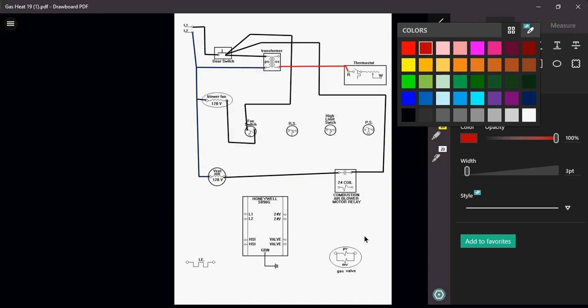Okay, our high limit switch, that's going to be a safety that's going to shut the furnace off if the furnace gets too hot. Rollout switch is going to sense the flame. It's going to sense whether or not the flame is rolling out in the wrong direction in the furnace. So how am I going to accomplish this? Well, I have to actually do this off of my W, off of my thermostat. And I'm going to actually wire my safeties and the coil on my relay here in parallel.